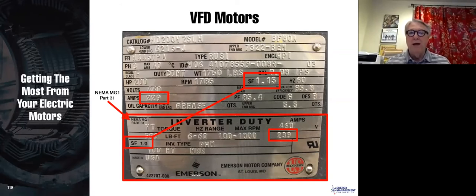Most motors are not going to have all this information, but you'll notice that the top part of this nameplate has the regular motor information, and it has the data for running the motor across the line, and the bottom gives you specific data for the motor running on an inverter or a variable frequency drive. Now let's notice first over here on the upper left of the inverter duty portion of the nameplate, it says NEMA MG1 Part 31. That's the first thing we want to look at because that has to do with the insulation, and we will cover that in a moment.